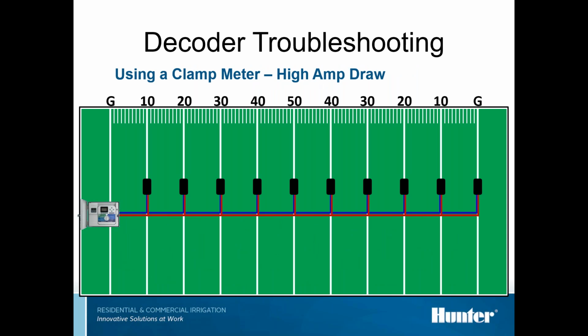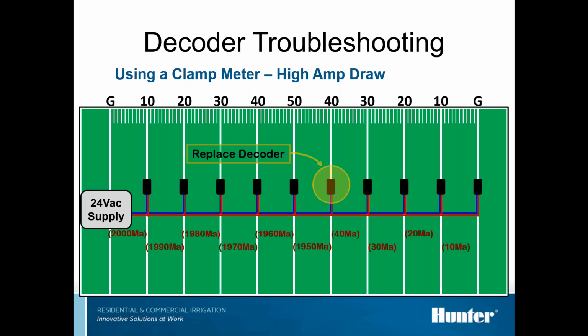Now, if you have a high amp draw at the controller and you take it off and you put the path on, the transformer on, here's a typical numerical thing that you would see with a clamp meter. Sometimes it's even high enough that it'll keep shutting it down. But if you're at 2000, and you clamp the next one, 1999 or 1990, 1980, it's dropping down until you get about halfway, you go from 1950 down to 40 milliamps. So that pretty much tells you where it dropped.